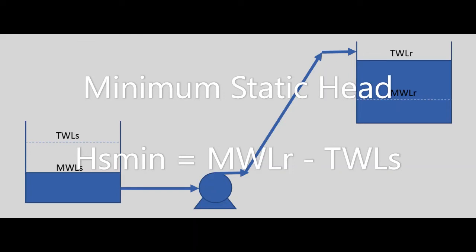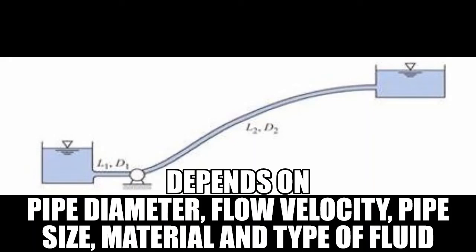Next, we will determine the frictional losses. The frictional losses is also termed as major losses as it is depending on the pipe diameter, flow velocity, pipe size, material and the type of fluid being conveyed. To calculate the frictional losses, the formula used is Darcy Weisbach equation. HF equals F times L divided by D times V squared divided by 2 times G. L is the length of the pipe, D is the pipe diameter, V is the flow velocity, G is the gravity.